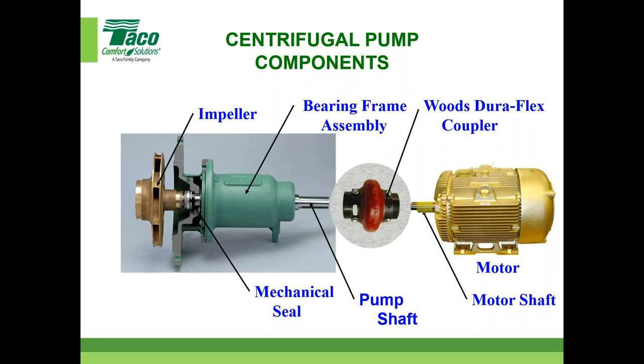Yes, there's a benefit as long as you remember to remove it. As a matter of fact, the Taco suction diffuser has a startup strainer in there that's very fine mesh. That needs to be removed after startup. But yes, there is a benefit to help alleviate the potential for mechanical seal failure during the startup period.